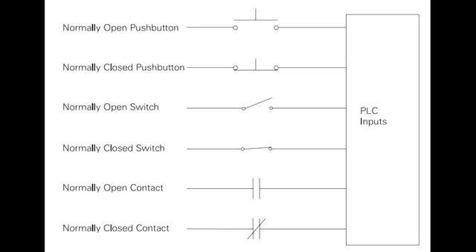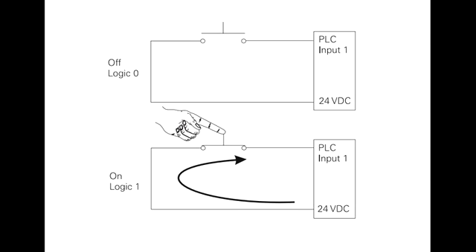A normally open, NO, pushbutton is used in the following example. One side of the pushbutton is connected to the first PLC input. The other side of the pushbutton is connected to an internal 24VDC power supply. Many PLCs require a separate power supply to power the inputs. In the open state, no voltage is present at the PLC input. This is the off condition. When the pushbutton is depressed, 24VDC is applied to the PLC input. This is the on condition.